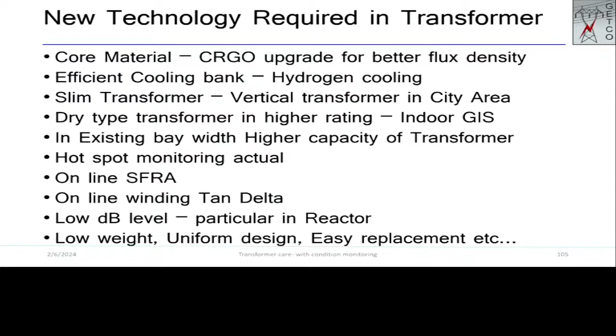Now, some new technology is required in transformers. Core material should be upgraded for better flux density, and efficient cooling banks are required. We now require slim transformers, vertically high, but accommodated in industrial or city areas. Dry type transformers are required for indoor GIS, and in existing bays we need higher capacity transformers. Hotspot monitoring is also important, and we try to monitor the transformer by online SFRA, online winding tan delta, and low dB level, particularly in reactors, with low weight and uniform design.